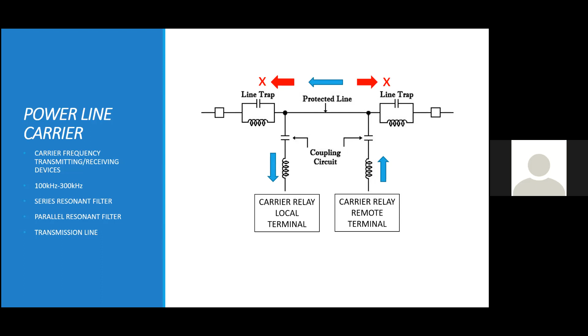So what's the difference between a series resonant filter and a parallel resonant filter? The series resonant filter is nothing but the line tuner, and the parallel resonant filter is nothing but the wave trap. The line tuner is a kind of LC series filter, which at its resonant or tuned frequency acts as a complete short circuit to that frequency. The opposite is true for a parallel resonant circuit.